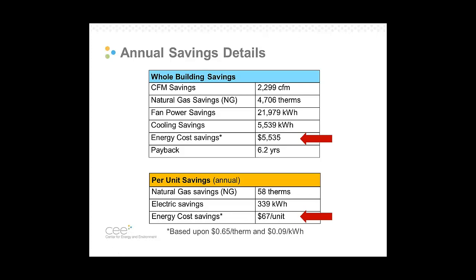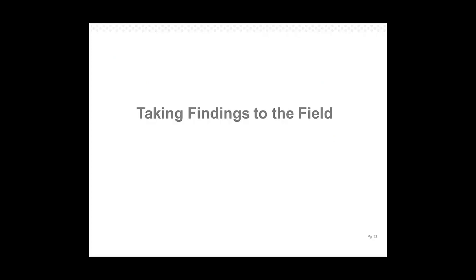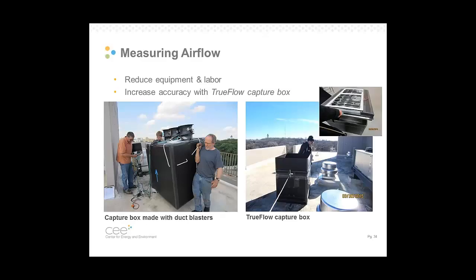Overall, when you put together the energy savings from the kitchens and the distribution improvement on the baths, we still came out with a decent amount of energy savings, about $5,500 per year, which yielded about a 6.2-year payback. That's a little bit longer payback than we typically see with our energy saving retrofits, but because we're solving odor and moisture issues for these building owners, they're motivated to invest to improve the performance of that system.